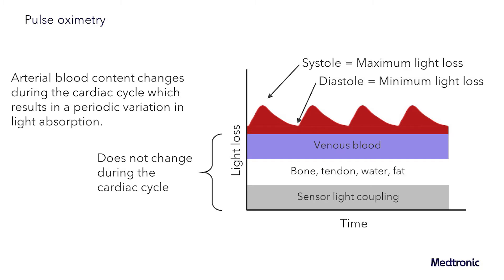There are constants within this formula for venous blood, bone, tendon, water, and fat, as well as sensor light coupling. These do not change during a normal cardiac cycle, but we will talk about some limitations that can impact this a little bit later.